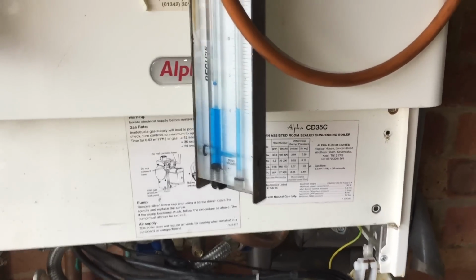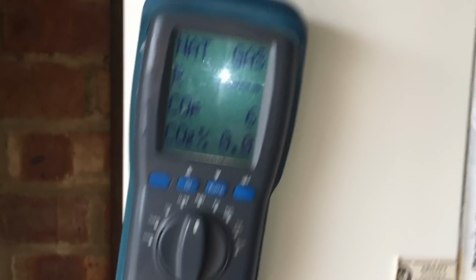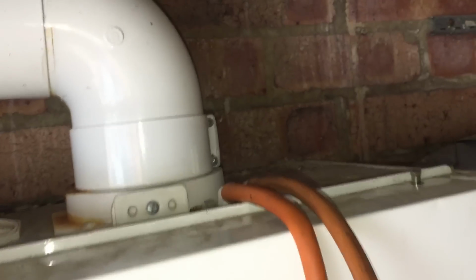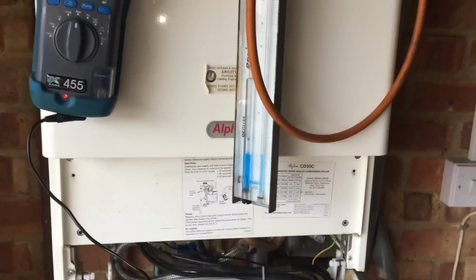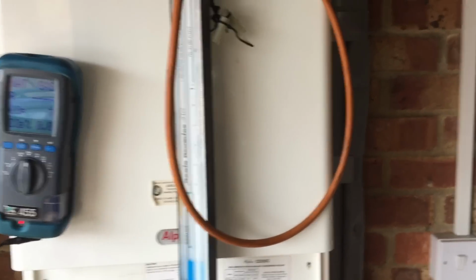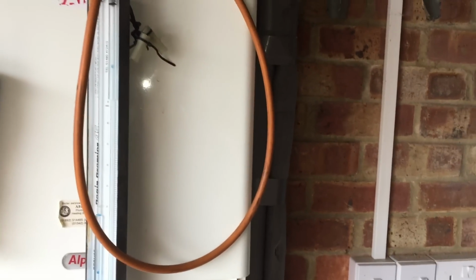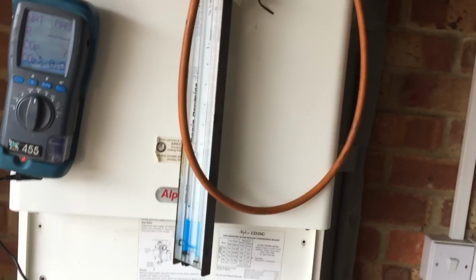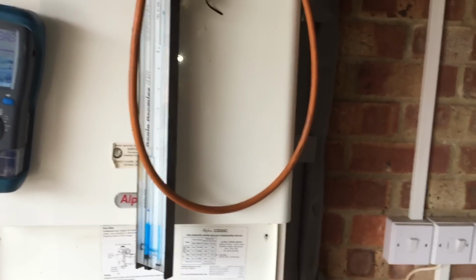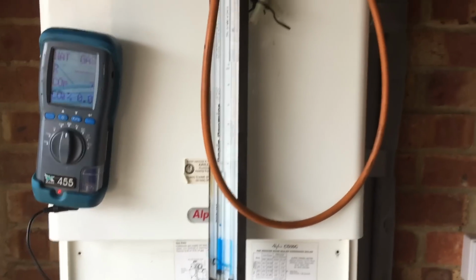Okay, so I've checked the MIs for this boiler, and I've got this disconnected, just purging itself, cleaning itself out. Providing this is correct, which it was, the combustion ratio just has to be below 0.0030. It's usually 0.0040, but on this boiler here it's 0.0030, and as you saw, we had a reading of much lower than that, so therefore this boiler is a-okay.